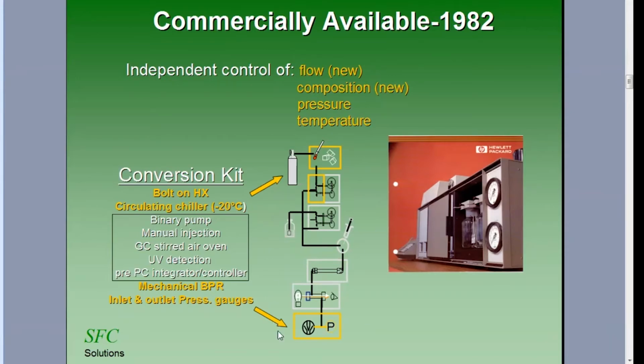You can see how complicated this thing is compared to the very simple hardware using a syringe pump and an FID. The main thing that was really different was that now you controlled flow at the pumps. The pumps were flow controllers, not pressure controllers. And also you can change the composition dynamically. You could actually do composition programming. Both these things were different from anything that anybody had done before.